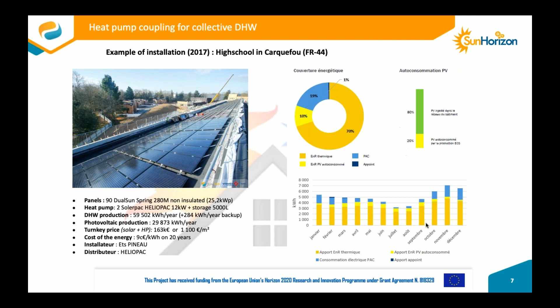Here you can see we have an average cost of 9 cents per kilowatt hour, so that's still great, below the price for the customer. Also important is the renewable coverage. As we are the cold source of the heat pump, the evaporator side, we have more than 80% renewable energy. The rest is the electrical consumption of the heat pump, but we also produce PV, and 80% of the PV production is directly self-consumed by the heat pump, so that's still better than 20%. It's really a low carbon and low energy consumption system.